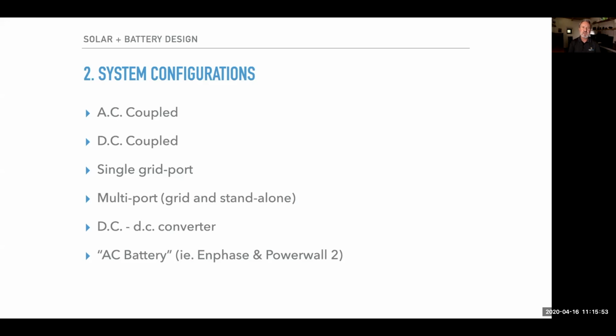We also have some with multiple ports, meaning they've got a dedicated grid port and a dedicated standalone port. There are DC-DC conversion devices that can be put between a PV array and an inverter, and there's this terminology, an AC battery. A battery by definition is DC, but once you put it into a package with an inverter inside, think of Enphase with their AC battery, or ACB for short, or Powerwall 2, which is an AC output device. People think of it as a battery, but actually it's got a 5 kilowatt inverter inside that pack. So it's sometimes referred to as an AC battery.